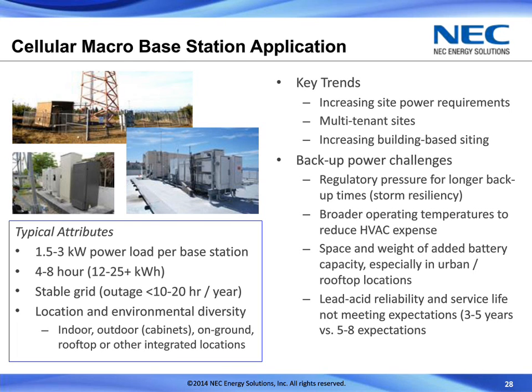Space and weight of added battery capacity, especially in urban rooftop applications. So this ties into the first two things I said. When you're adding batteries for power and for energy, with lead you might run into a lot of issues due to the weight. Buildings, a lot of times can't handle the additional weight load, and also there might not be space to put them since, because of the weight, they're typically limited to the first floor or the basement. Whereas the lithium is a lot lighter, you can put it really on any floor, or for new construction, it'll take up a lot less of your space budget, so you can do other things with that space, or, maybe due to the reduced weight, your construction costs are reduced. There's a lot of benefits there. Finally, the reliability and service life. Lead acid not quite meeting the expectations, seeing somewhere in the 3 to 5 year range versus 5 to 8 year expectations.